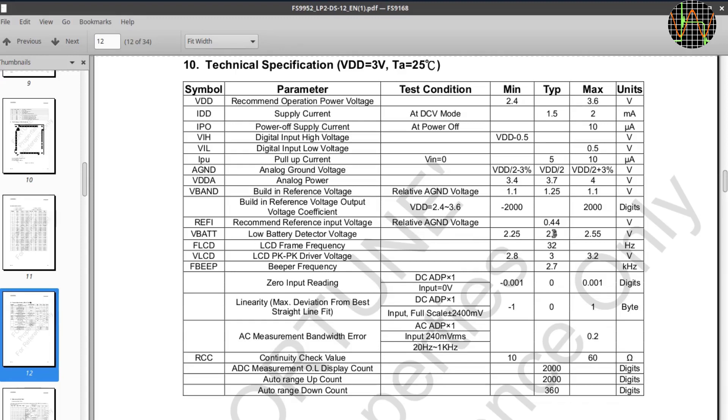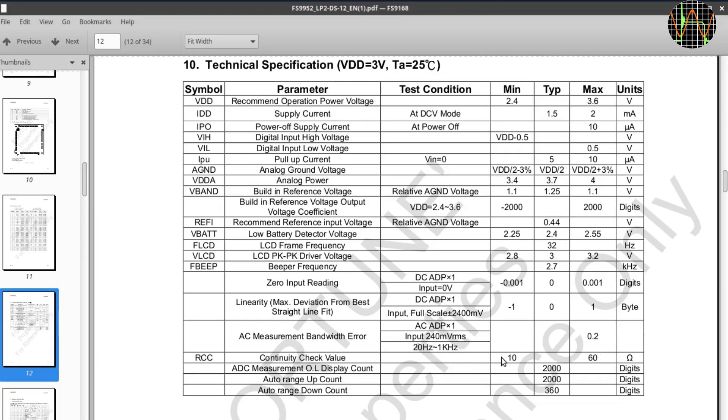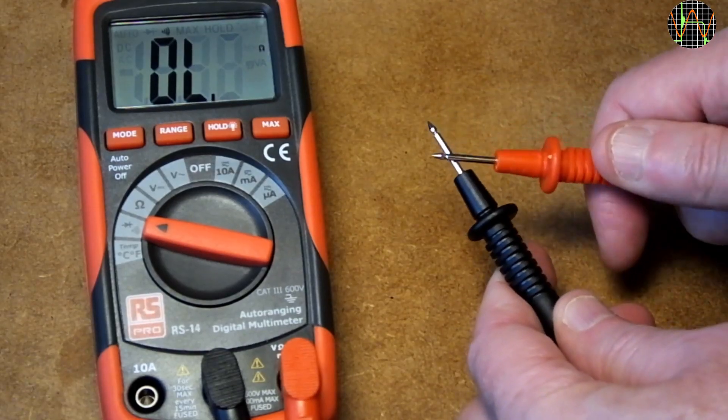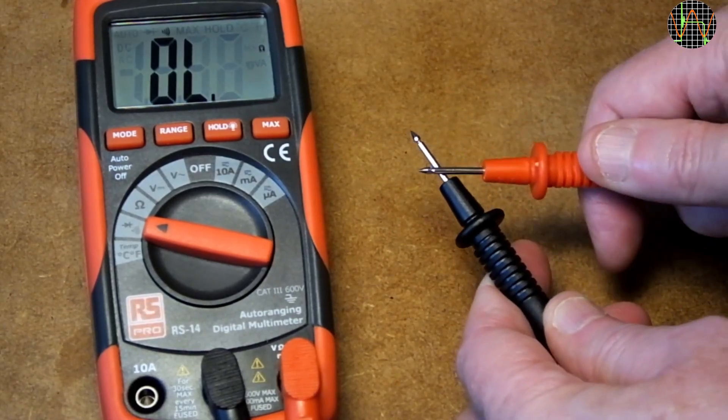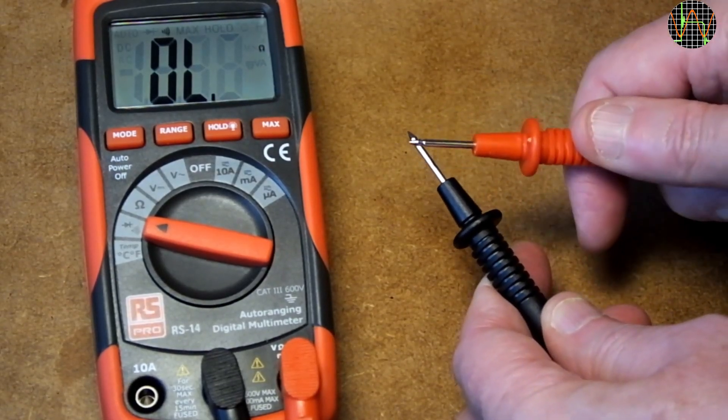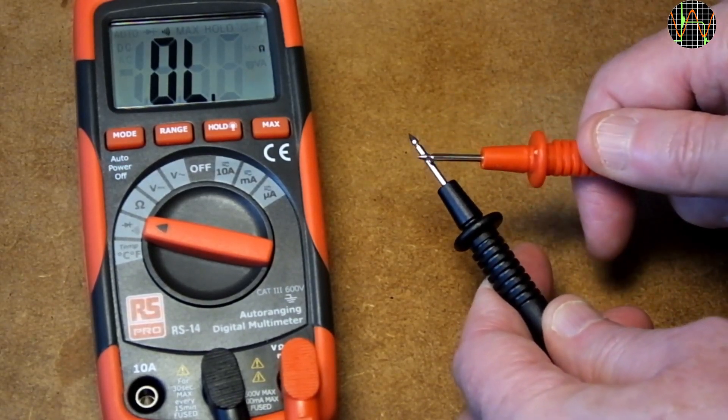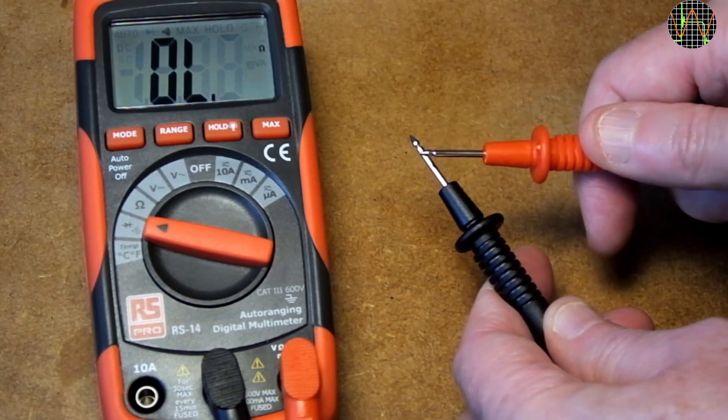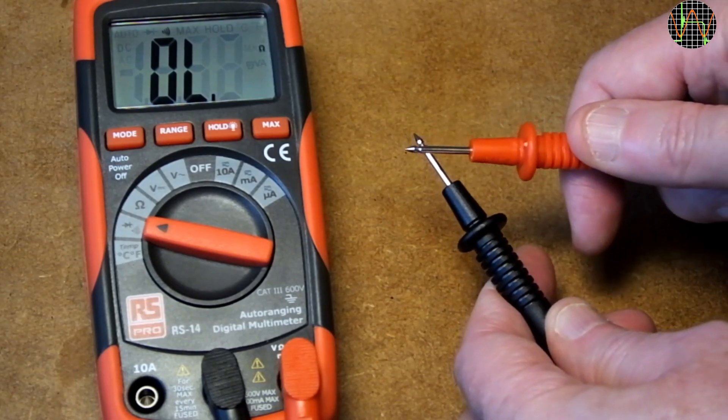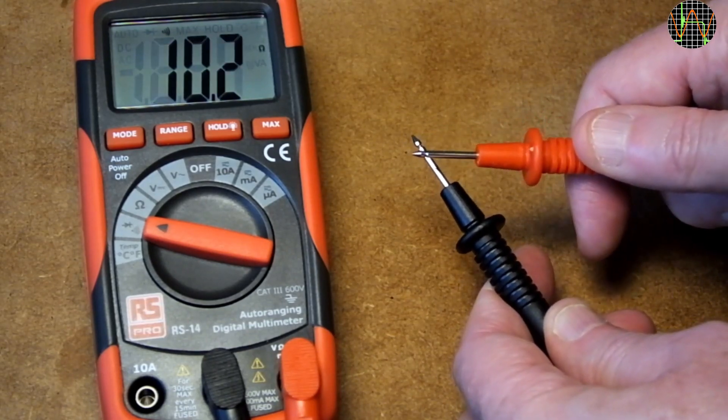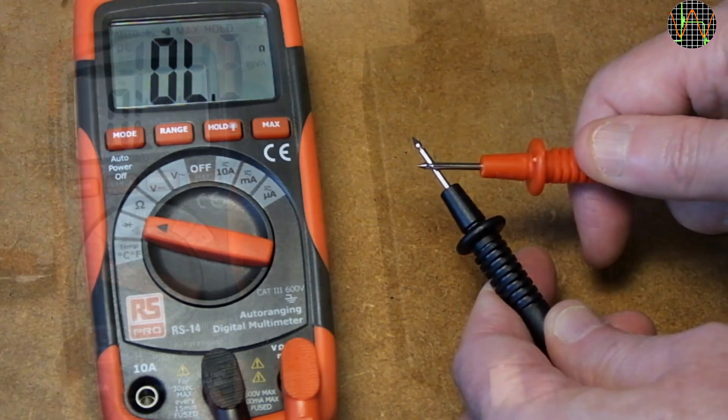Further we learn that the annoying beep is 2.7 kHz, but probably more useful is the AC bandwidth of 20 to 1 kHz and that the resistance limit for the continuity beep could be anything between 10 and 60 Ohm, which is a rather wide range. I already showed that continuity isn't one of the strong points of this meter.